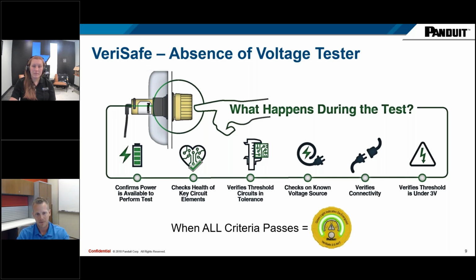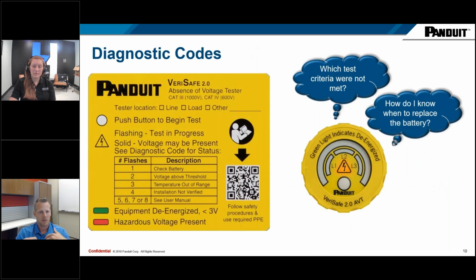What happens if it fails? It's going to give you a flash code. It'll tell you, hey, something's not right. Something is not passing my set of criteria. It could be checking the battery. It could be, hey, the voltage is still 120 volts, still 480 volts. Don't enter. Something's not right. Something's too hot. Couldn't verify the installation. That number of flashes right there, number 4, it'll flash back at you and at least give you the initial breadcrumbs of here's why I failed, more or less. And then you can go off and start figuring out, okay, now I need to troubleshoot. You might need to put on your PPE if you need to go into the cabinet and do it the old-fashioned way, right? But it will not give you a green light if any of those criteria failed.